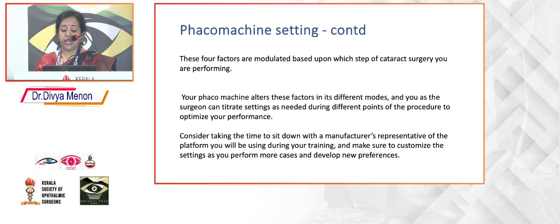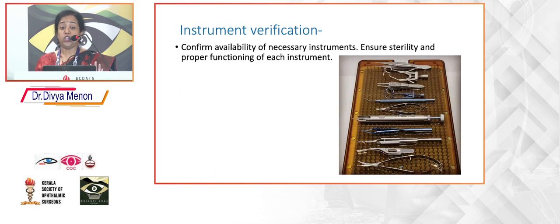You have to take time and sit down with the manufacturer's representative of the platform you'll be using during your training, so that you can customize the phaco settings to your convenience during your initial surgeries. This is very important, because they must have seen so many cataract surgeons operating, so they will adjust the phaco machine settings to your convenience. And instrument verification is again very important. Confirm the availability of all the necessary instruments. Ensure the sterility and proper functioning of each instrument. You must be comfortable using all these instruments as well.